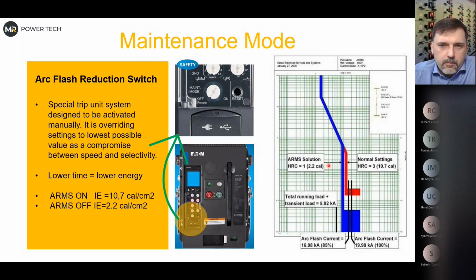So for a period of time, our safety is more important than selectivity in the system. We can sacrifice selectivity, make the breaker not selective, but very fast. And because of this, we reduce the energy on the part of the system behind the breaker that we are working on. It depends on the manufacturer, of course, but it works in a very similar way. We still have to operate our system, so if you have some 2000 amp, 3000 amp load, we still have to keep it. This will not change. The only thing that will change is the short time and instantaneous settings.